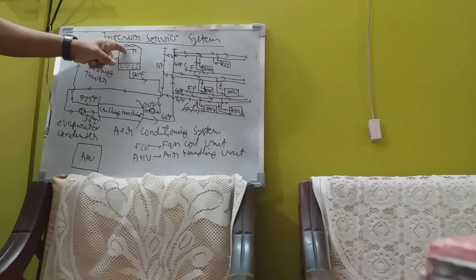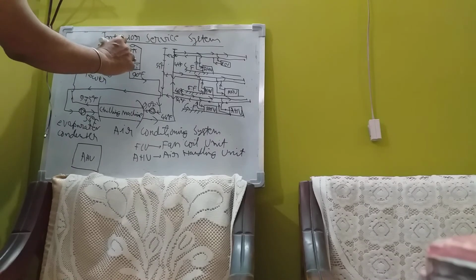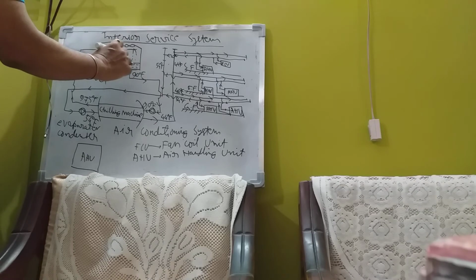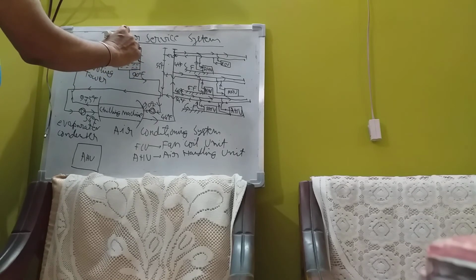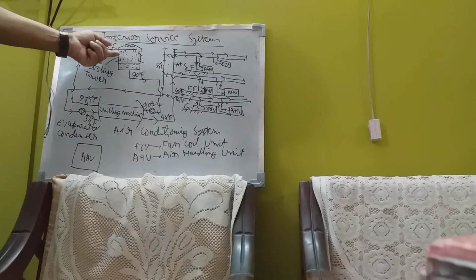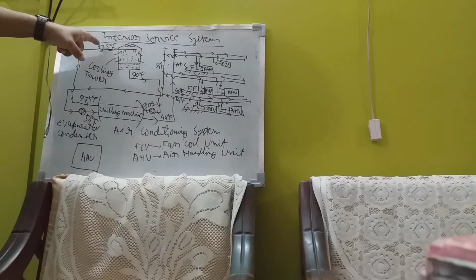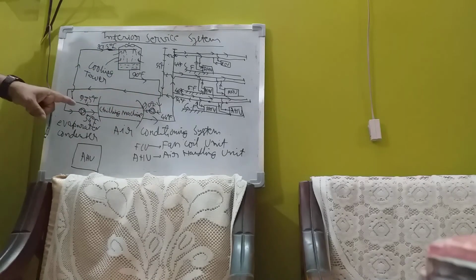At the cooling tower at 97.5, as water falls through the cooling tower, air is passed through that. As the air is passing, it picks up heat. Air picks up heat, this water becomes cold. So it becomes cold from 97.5 to 90 degree Fahrenheit and again comes back to the condenser system.